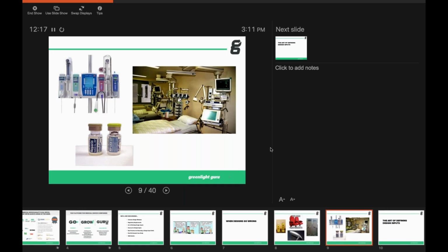It could be you have a device that's used in an ICU and there's all sorts of things going on, all sorts of other gadgets, devices, equipment, bells, alarms, displays, all sorts of things happening. And if your product is just going to be added to that mix of chaos and it starts making a noise with all these other things that are out there, that can not make life simpler. It can actually make it more confusing and more challenging.